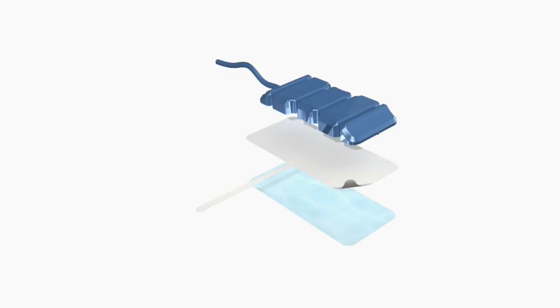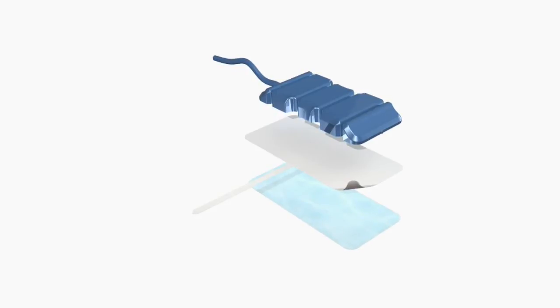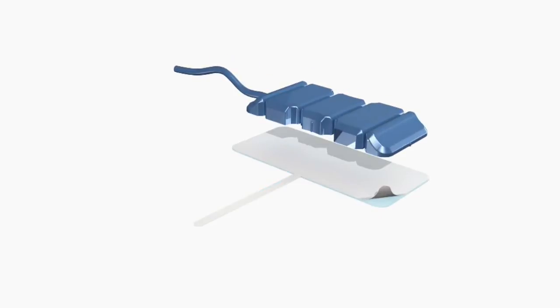During the clinical study performed in this department, we experienced a contrast extravasation not detected by palpation but clearly seen on the SimpliDetect system. We once had a case where SimpliDetect identified a falsely set 3-way valve and avoided unnecessary radiation to the patient. NeoRad has developed a unique double-faced adhesive with a sonolucent material. That is, it enables sound to travel freely through it.